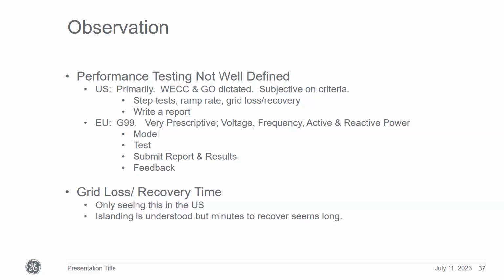In Europe, there's a document called G99, very prescriptive on voltage, frequency, active and reactive power. It steps you through the modeled cases, the type test data needed beforehand, and tests to be performed at commissioning. Once those tests are done, we submit detailed reports and results with CSV files at whatever time intervals are required, and very often we get feedback on those tests. So it seems to be a more closed loop process in Europe.